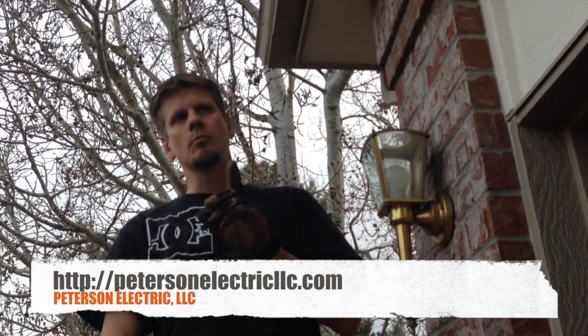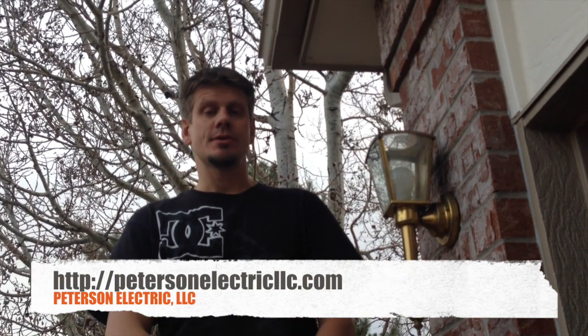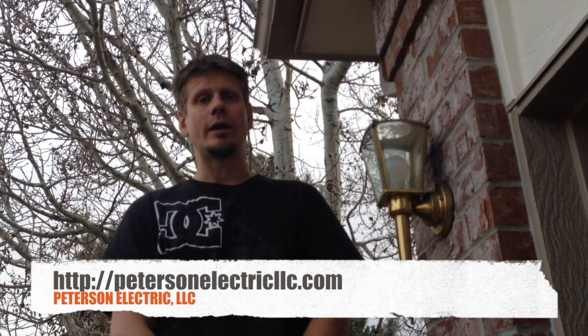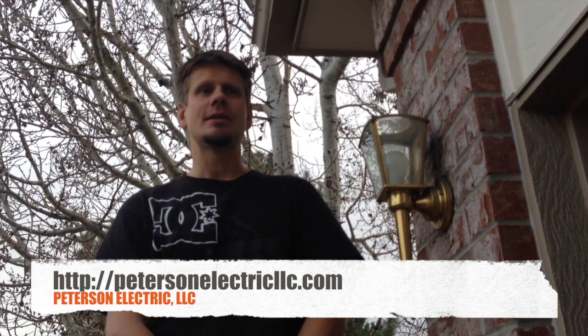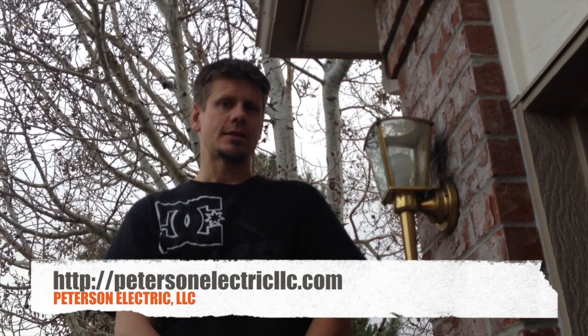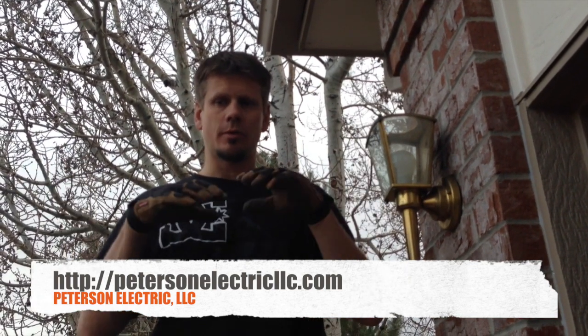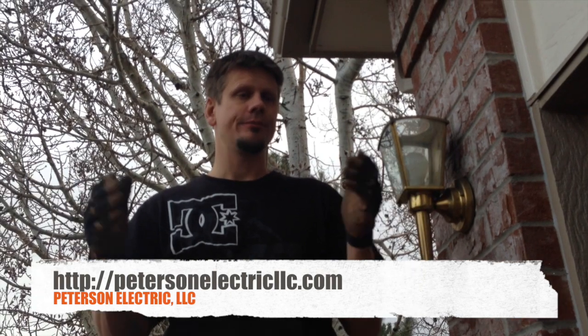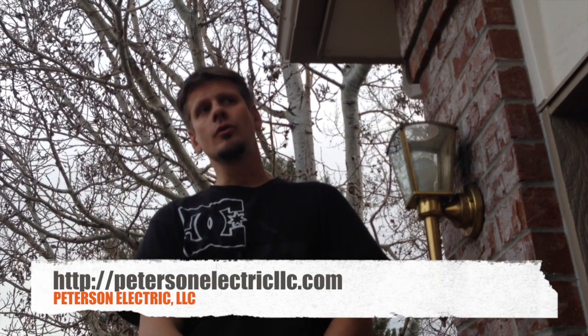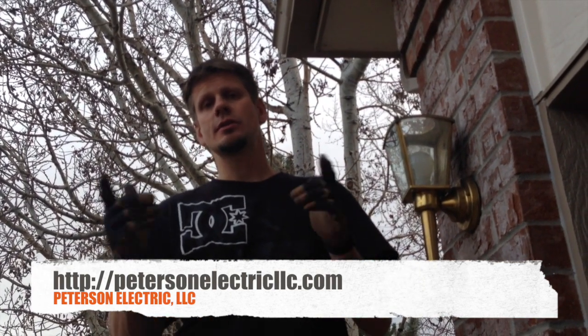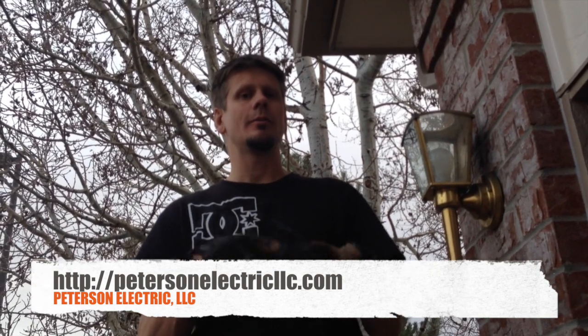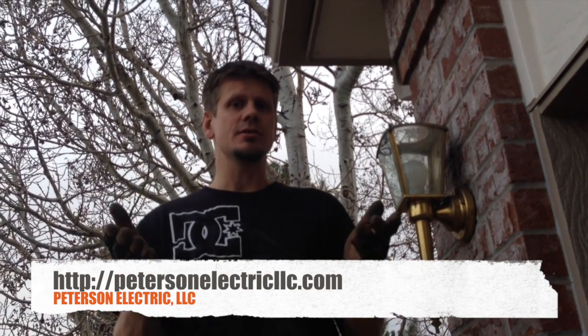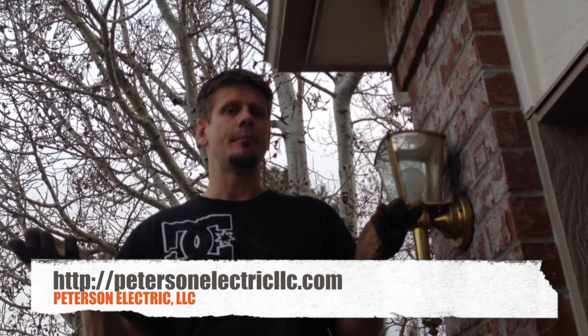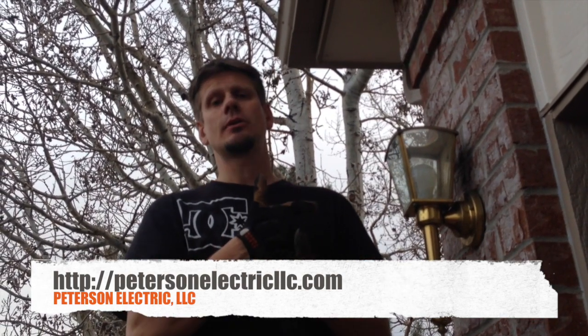So number one, I look at the year of the home. This one is a 1996, so I know the wiring in it. I doubt it's anything significant, but it does tell me that all those areas of the home are probably three separate circuits. If I have three circuits having an issue, by the age of the home and how it's wired, plus the size of the home being about 2,200 square feet, I know it could possibly be in the panel.